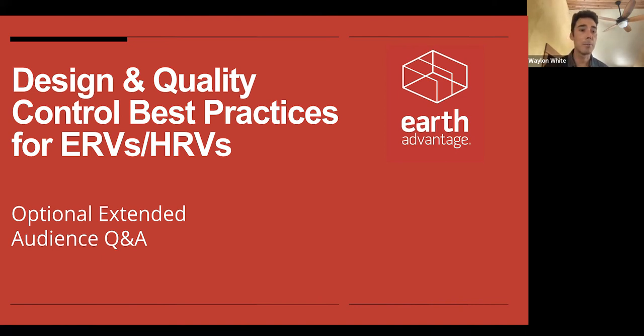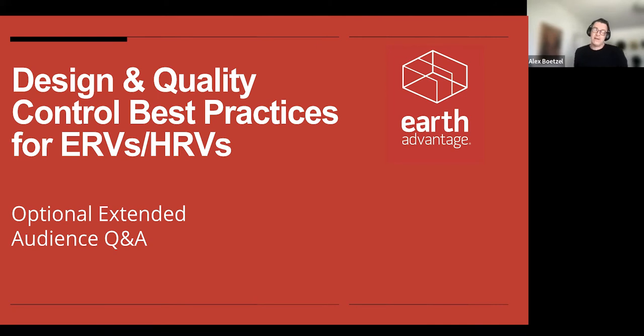That's probably part of why you tend to select those for your projects, Alex. Yeah, we're talking about looking for 80% and better. Other numbers you'll see are at least 75% and better. I think LifeBreath is a solid unit, but that's kind of where they max out in terms of efficiency. A note on these numbers: there are two you'll see, the SRE, sensible recovery efficiency, and the ASE, apparent sensible recovery efficiency. One only addresses the core and tends to look better. The other, SRE, I think is the more important one to look at, because it takes into account the leakage rate of the housing and waste heat of the fan motors, so it's the more useful number. If there's a lot of numbers on these sheets, and you're looking for just one, that's the one.